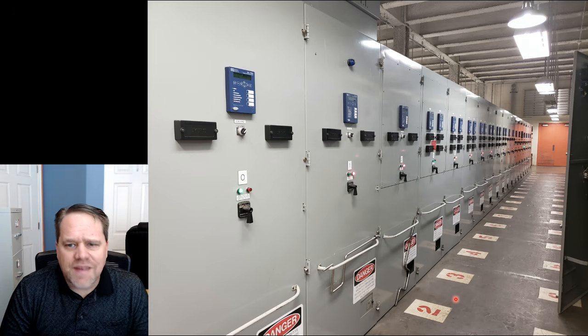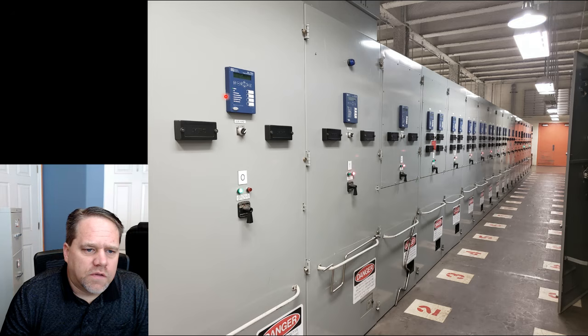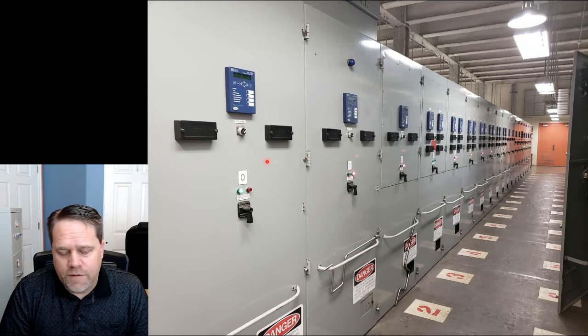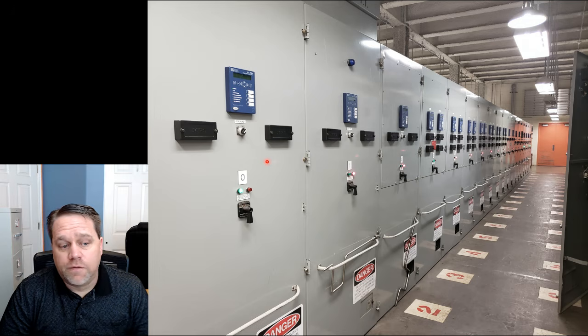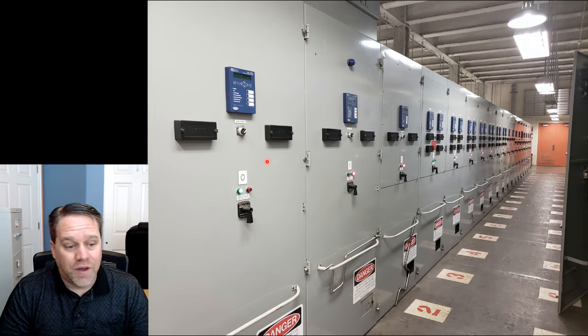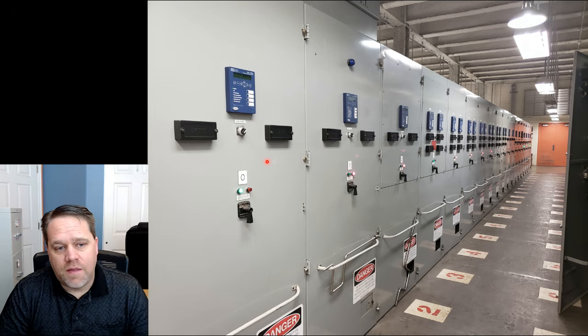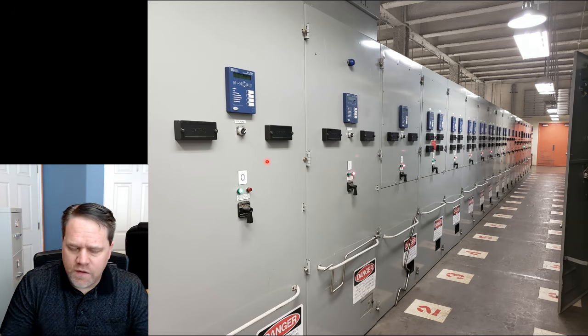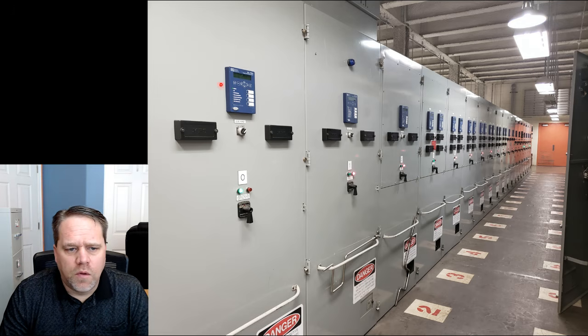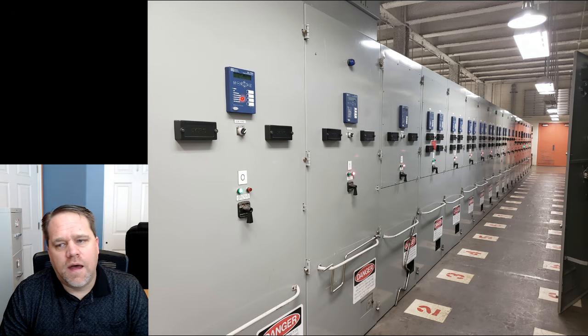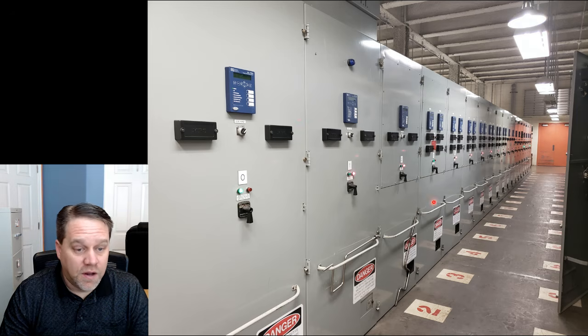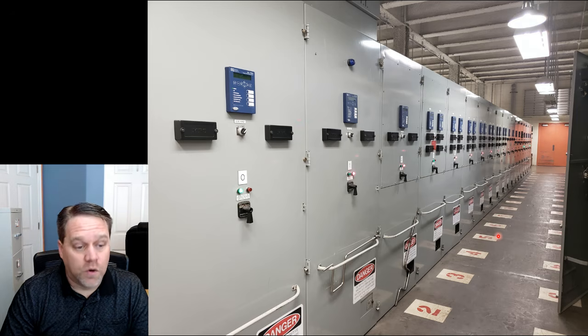It's a staggering amount. Each of these little blue things up here is something that, if you're not familiar with, you should be. If you're into the National Electrical Code, 240.67 and 240.87 both talk about it — that's an arc energy reducing maintenance switch. I'll go over that in a minute, but they have these on every single switchboard and switchgear in the facility, and that's 100% for worker safety, which I think is great.